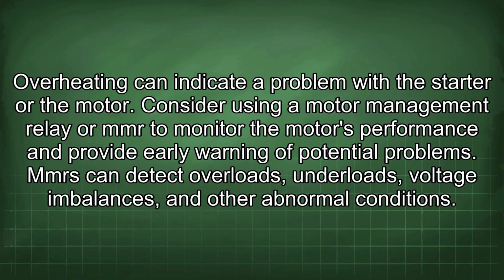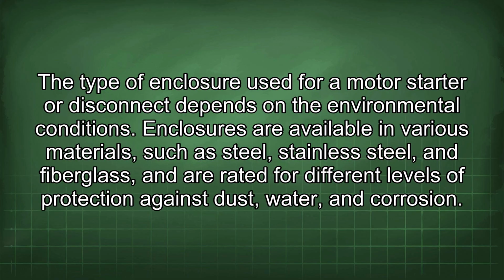Consider using a motor management relay or MMR to monitor the motor's performance and provide early warning of potential problems. MMRs can detect overloads, underloads, voltage imbalances, and other abnormal conditions. The type of enclosure used for a motor starter or disconnect depends on the environmental conditions. Enclosures are available in various materials such as steel, stainless steel, and fiberglass, and are rated for different levels of protection against dust, water, and corrosion.